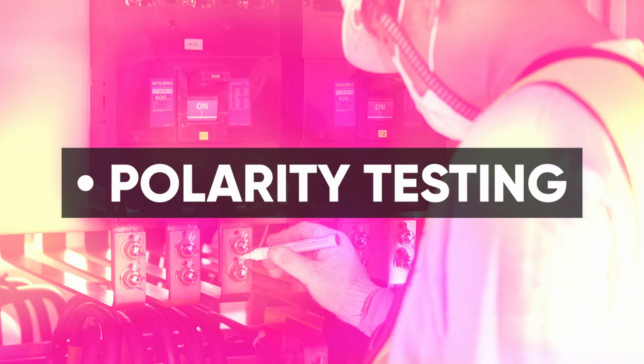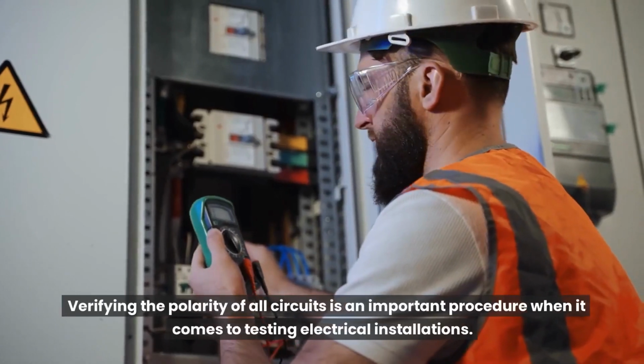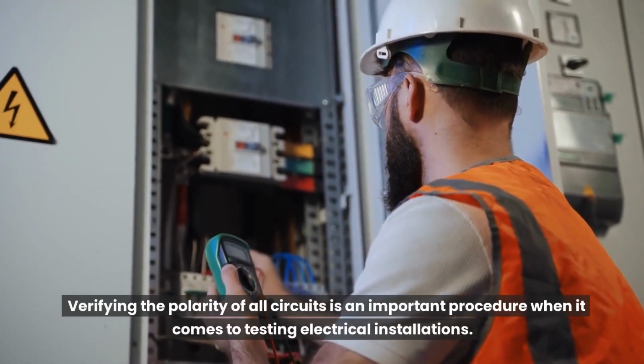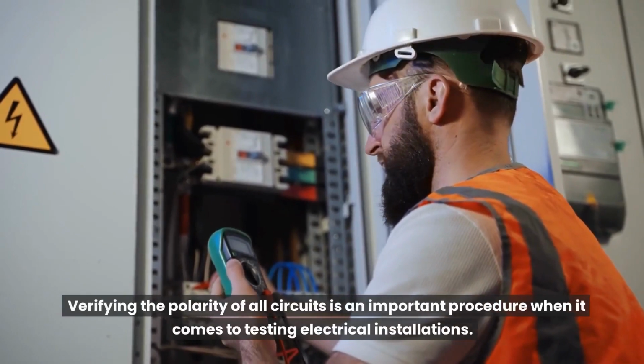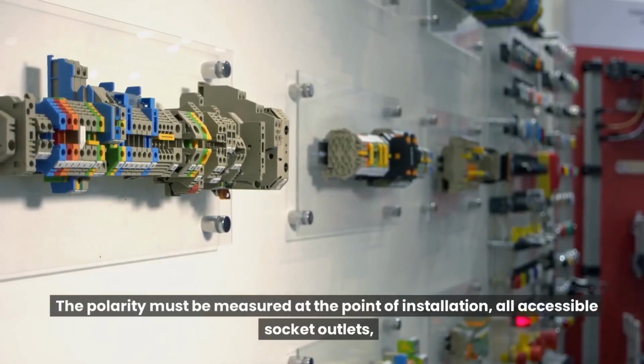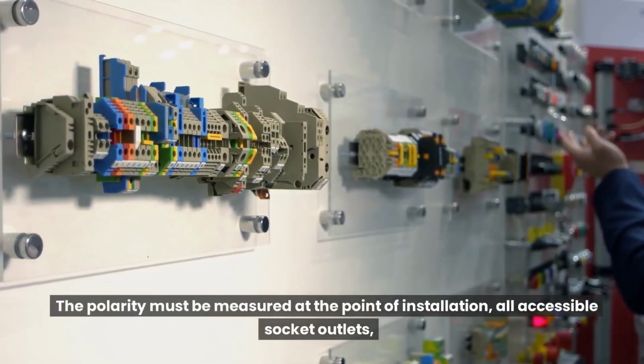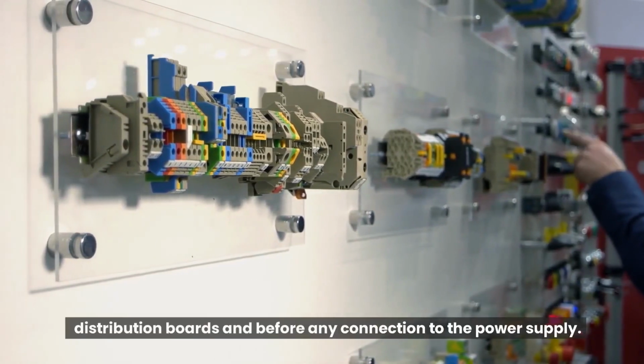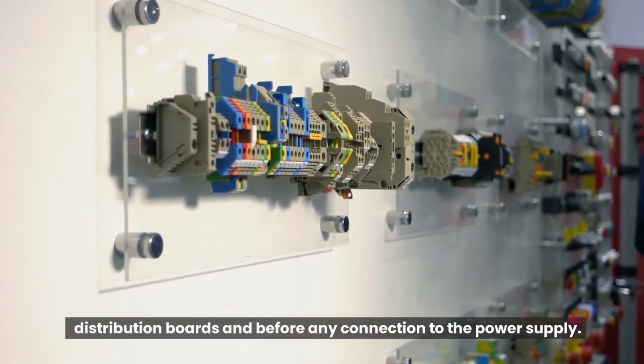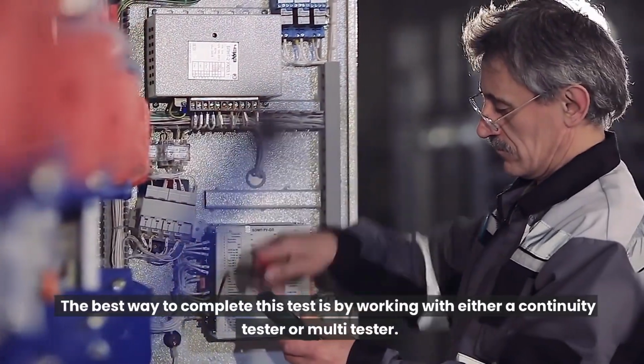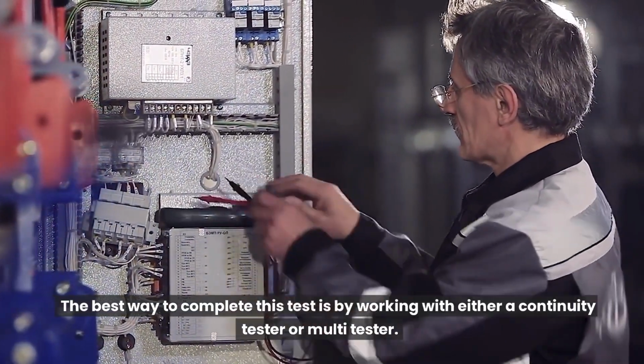Polarity testing. Verifying the polarity of all circuits is an important procedure when it comes to testing electrical installations. The polarity must be measured at the point of installation, all accessible socket outlets, distribution boards, and before any connection to the power supply.